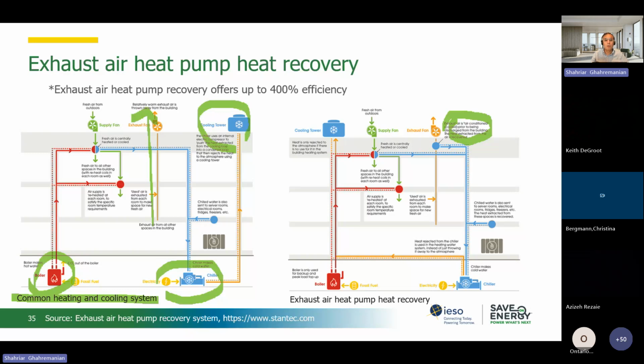And also the size of this equipment will go down, becomes smaller: the boiler, the chiller, and the cooling tower, because now we have an extra source that is running all the time, because these exhaust fans need to work. So this is year round, and we can take advantage. I encourage that if you have such a thing, go and check these kinds of applications. So this is a good integration of a heat pump and a heat recovery system.